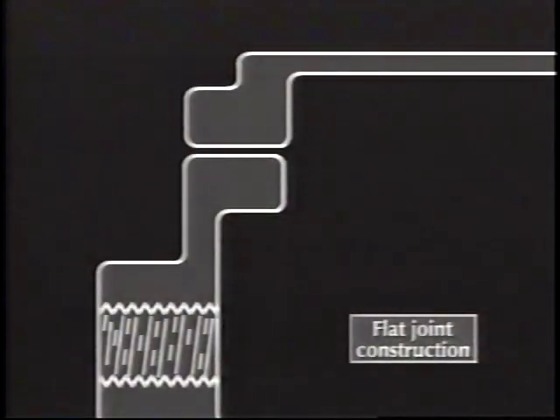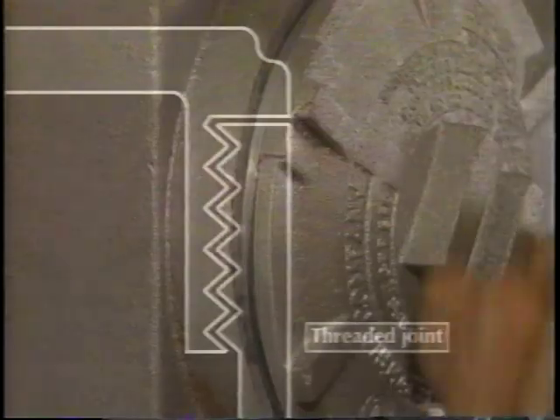Here's an example of a precision ground joint design. The thick walls contain the internal explosion. The ground joint cover allows the gases to slowly escape at a cooler temperature. This threaded joint design features a cover with a minimum of 5 threads that engage with the body. When an explosion occurs, the force pushes the flames and hot gases around the 5 threads, allowing them to cool and escape harmlessly.